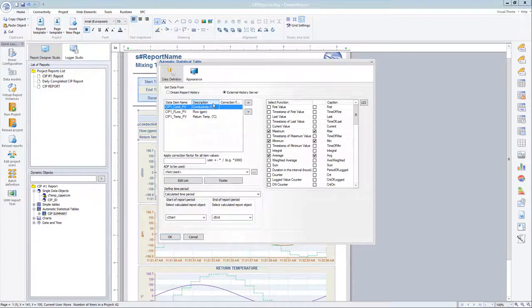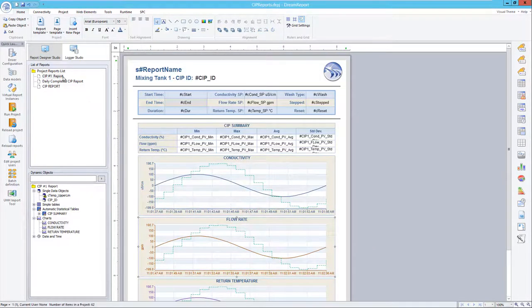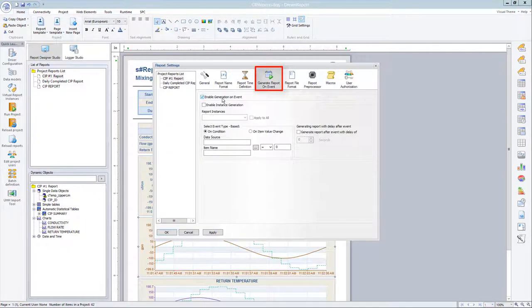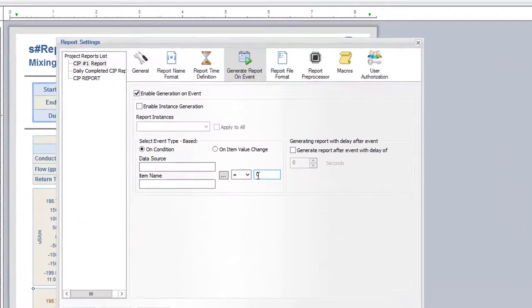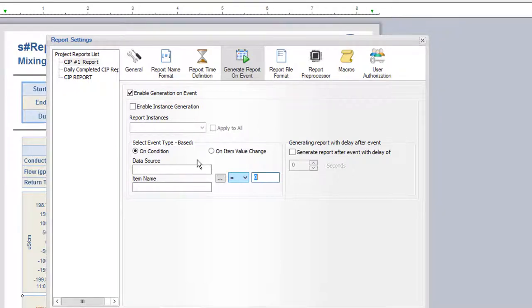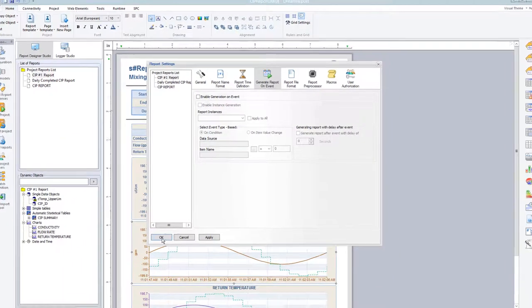This report could be generated on demand, or you might want to automatically generate it when the CIP cycle completes. We would use the DreamReport event generation option in the report settings. If we had configured a communication driver to access live data from a PLC or HMI, we could then point to the CIP status tag and trigger the report when that tag equals zero.